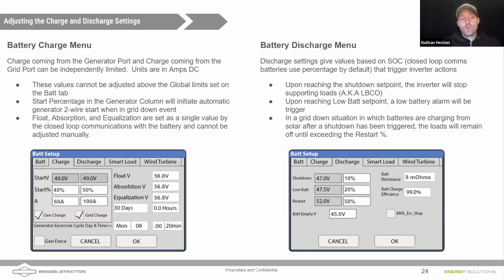You have the ability to limit how much charging you're pulling from the utility. And here we show it limited to 100 amps. These are variable settings. You can set them to what makes sense for you. If you have a generator connected to the grid port, there's a checkbox that you can check. I'll show that later. If you have a generator connected to the gen port, then the right column percentage there is what triggers the 2-wire start. So this percentage is the 2-wire start signal when you have a generator connected to the grid port. And then the one on the left, the 40%, is when you have a generator connected to the gen port.